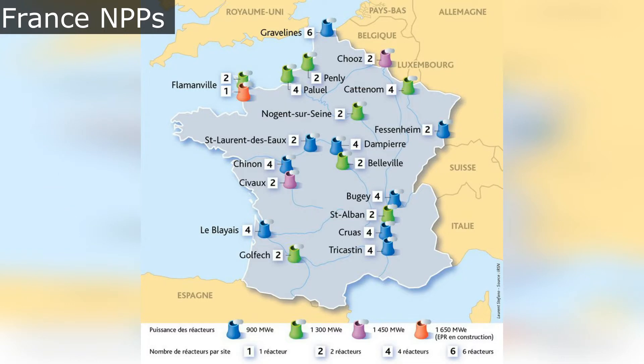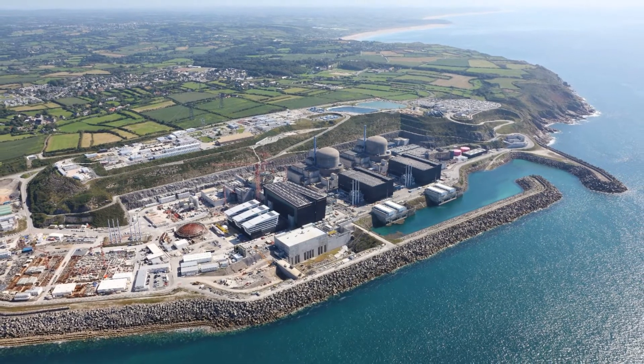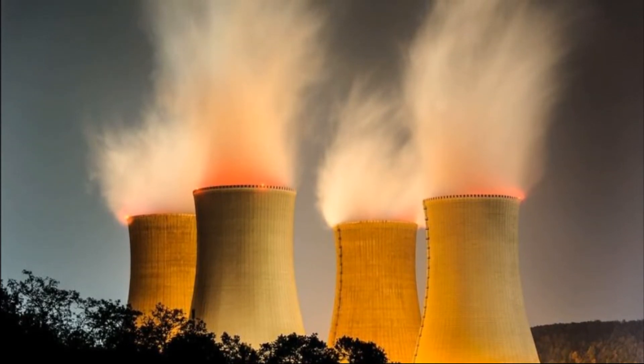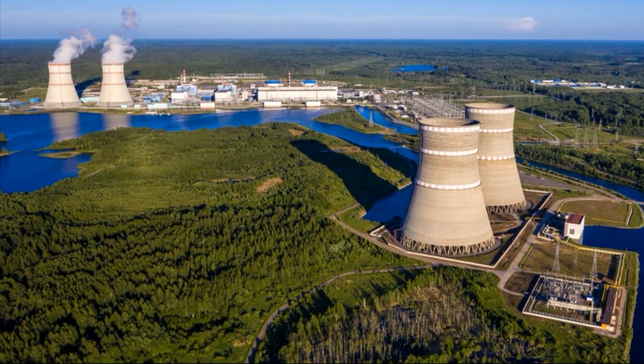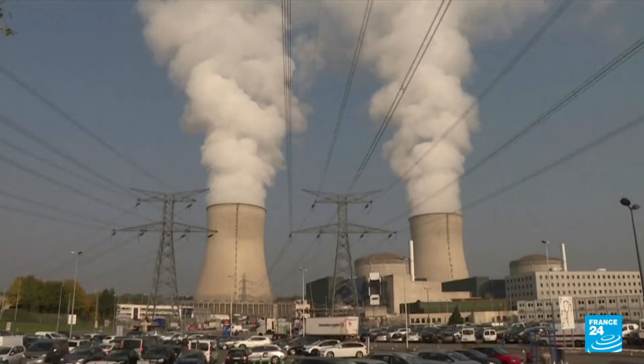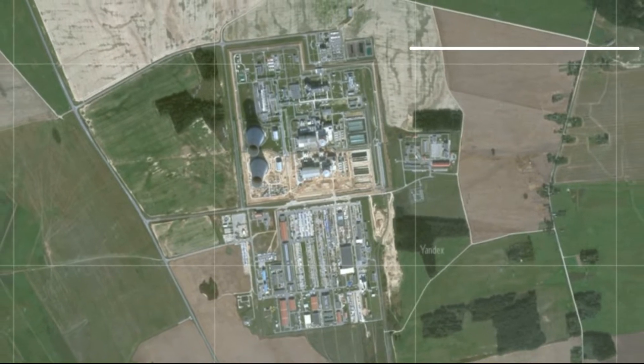The restrictions primarily apply to nuclear power plants located on rivers. Four of the 18 French nuclear power plants are located on the seashore — these standards and heat waves concern them to a lesser extent. Another 10 nuclear power plants in mainland France use cooling towers for cooling. In them, water evaporates and cools, and heat is directly transferred to the atmosphere, not to river water. With evaporation from the cooling tower, less than 1% of the water is carried away, and the rest goes back to the cooling circuit. Therefore, it is called a closed cooling circuit. Cooling towers need only a small water makeup, making it possible to build nuclear power plants even far from large rivers and reservoirs.